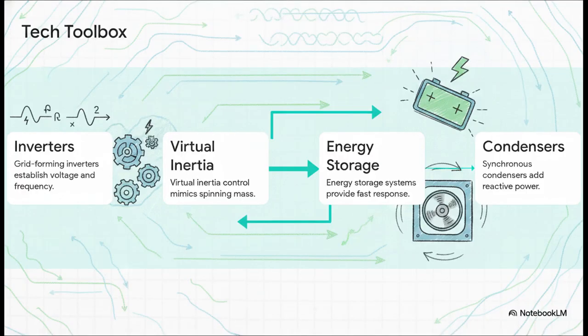To solve this low inertia problem, engineers are opening up a pretty wild technological toolbox. First, we're swapping out older, passive grid-following inverters for new grid-forming inverters that actively establish voltage and frequency on their own. Second, we're pairing those with incredibly fast-responding lithium-ion energy storage systems. Third, we're deploying virtual inertia control. And fourth, when we really need to brute force it, we install synchronous condensers. These are literally massive machines that just spin without a mechanical load, purely to inject real, physical inertia back into the power network.